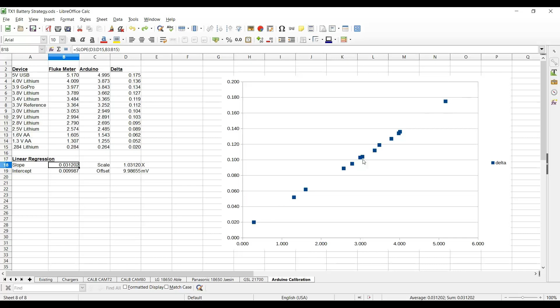Now what this gives us is these 2 numbers. The slope of the line, and if you remember back to freshman math, a line is y = mx + b. So the slope of our line is going to be 1.031202. So it's just a tiny bit off from a slope of 1. And the intercept is 0.009987, which is just a little tiny bit above 0. So that represents 9.98655 millivolts of offset.